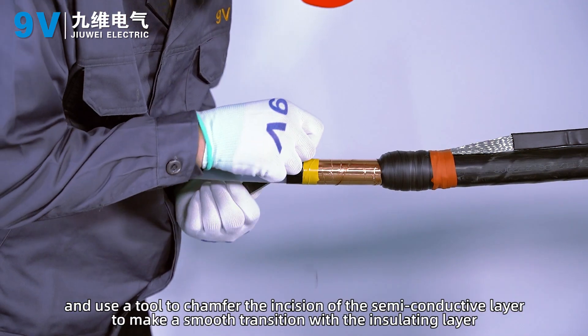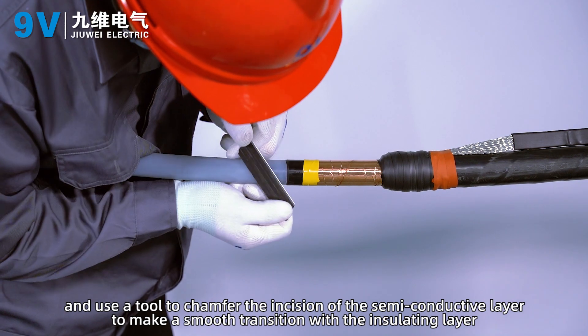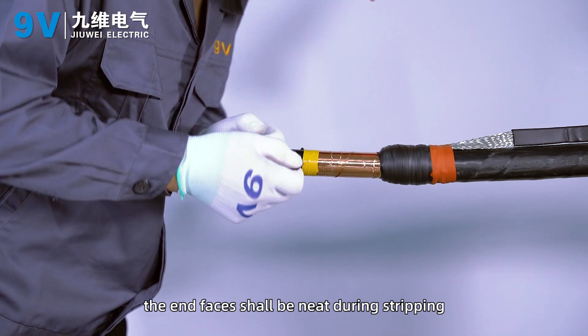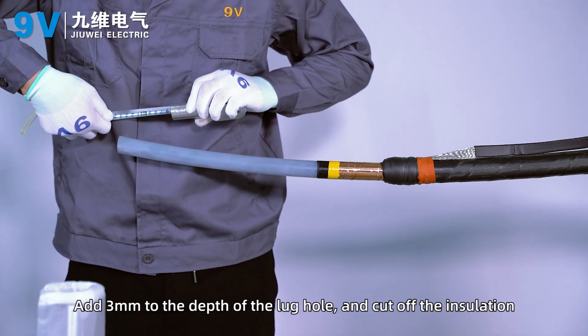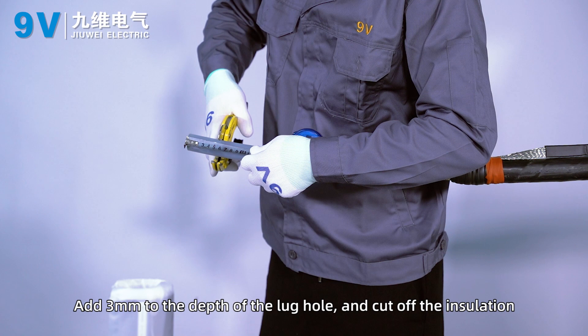Use a tool to chamfer the incision of the semi-conductive layer to make a smooth transition with the insulating layer. The end faces shall be neat during stripping and the insulation layer shall not be scratched. Add 3 mm to the depth of the lug hole and cut off the insulation.